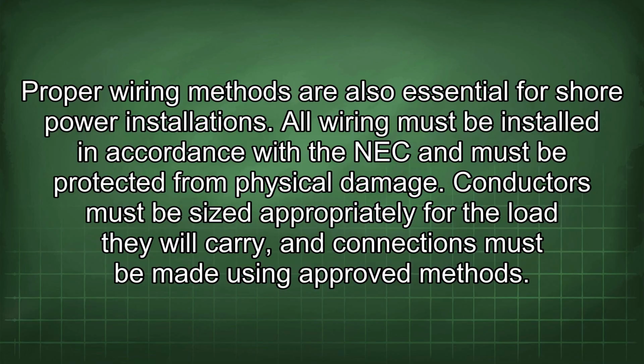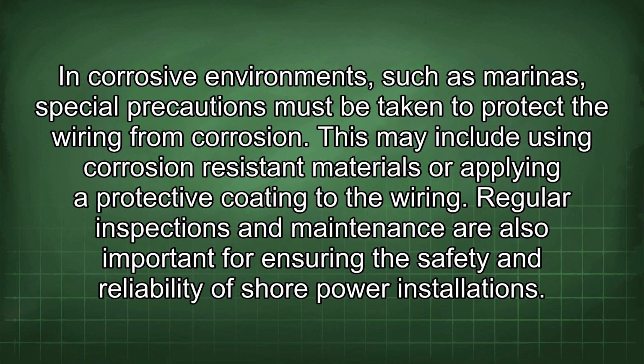Proper wiring methods are also essential for shore power installations. All wiring must be installed in accordance with the NEC and must be protected from physical damage. Conductors must be sized appropriately for the load they will carry, and connections must be made using approved methods. In corrosive environments, such as marinas, special precautions must be taken to protect the wiring from corrosion. This may include using corrosion-resistant materials or applying a protective coating to the wiring.